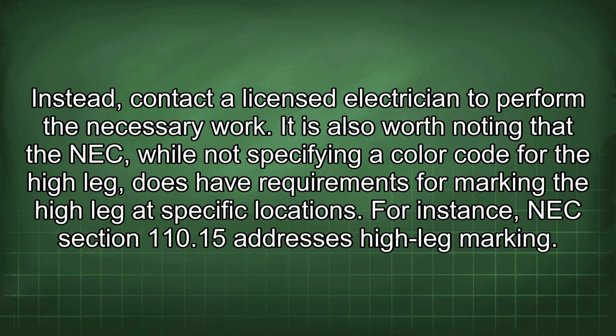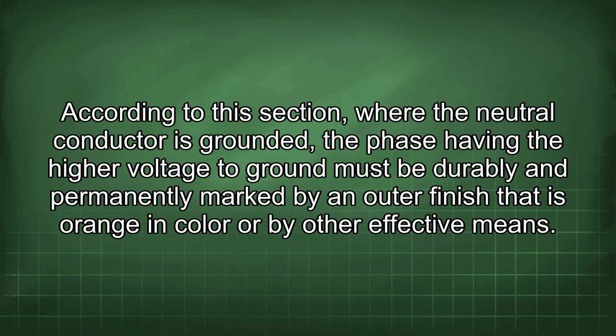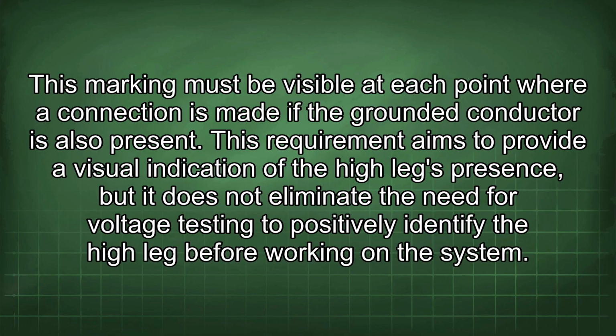It is also worth noting that the NEC, while not specifying a color code for the high leg, does have requirements for marking the high leg at specific locations. For instance, NEC section 110.15 addresses high leg marking. According to this section, where the neutral conductor is grounded, the phase having the higher voltage to ground must be durably and permanently marked by an outer finish that is orange in color or by other effective means. This marking must be visible at each point where a connection is made if the grounded conductor is also present.